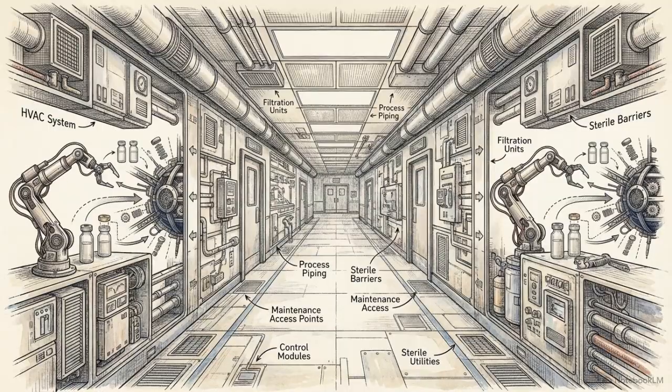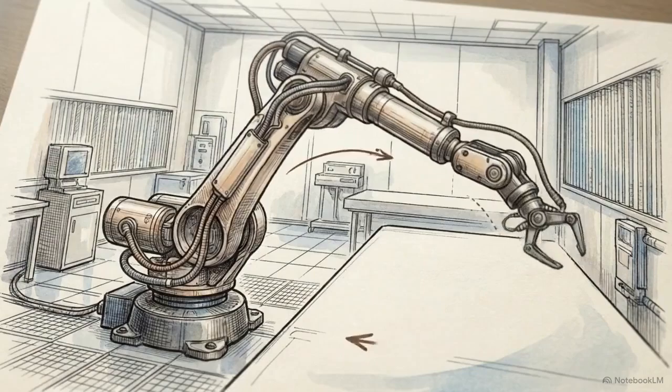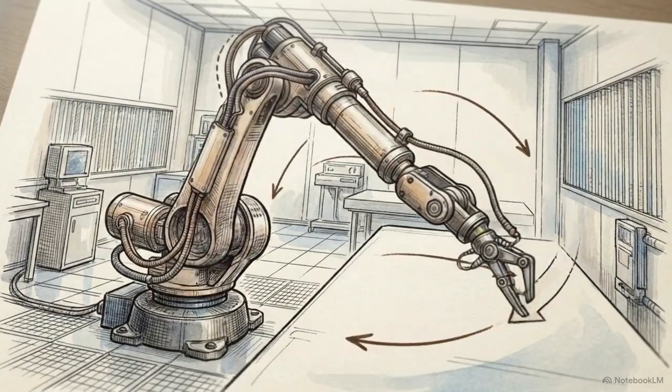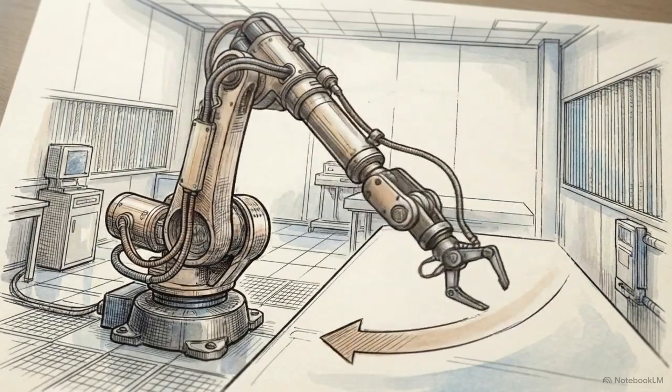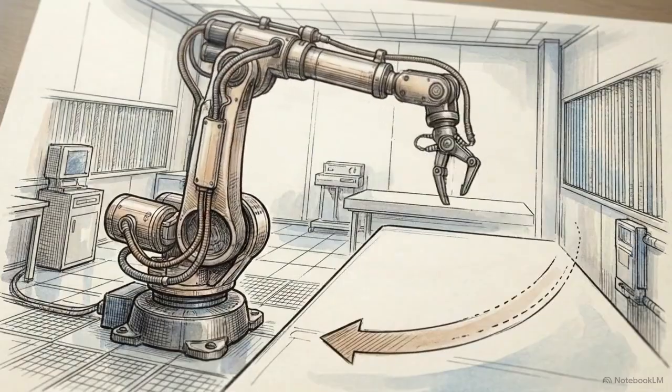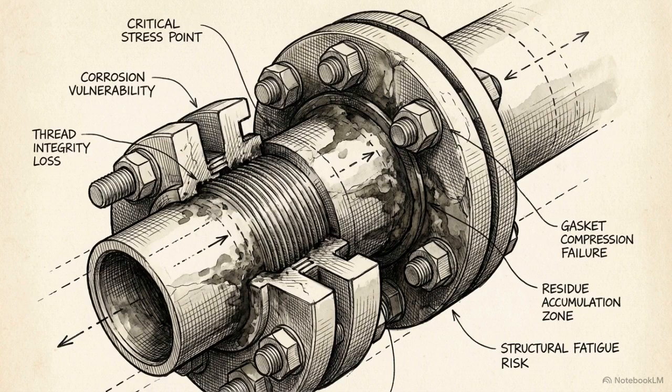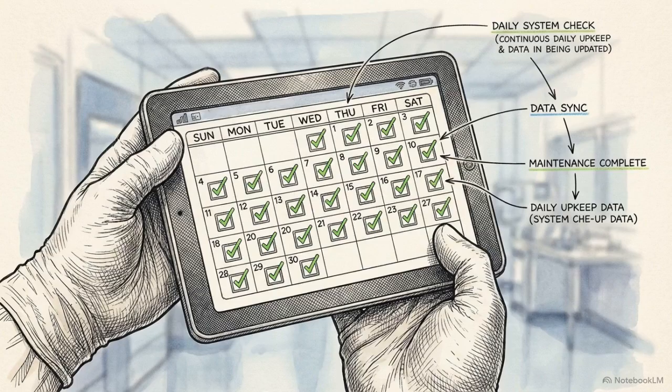The final domain is physical plant maintenance and sanitary conditions. In this aseptic cleanroom, maintaining the sterile environment requires continuous monitoring and strict adherence to validated cleaning cycles. Relying on worst-case cleaning scenarios that do not reflect your hardest-to-clean products creates a systemic vulnerability. Inspectors now expect documented daily facility upkeep rather than a deep clean performed solely in anticipation of an audit.